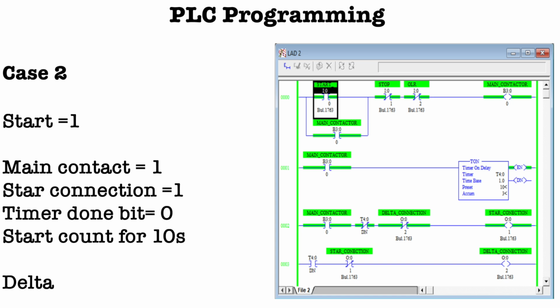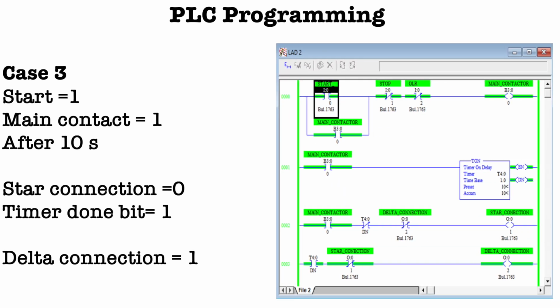At the same time, you can see my star connection is getting supply. That's why you can see in the third rung the output is represented by 1, right? And you can see in the fourth rung, when the star connection is high, it is represented by the normally closed contact. That's why it makes the fourth rung open. That's why my delta connection doesn't get any supply because of the interconnection, right?